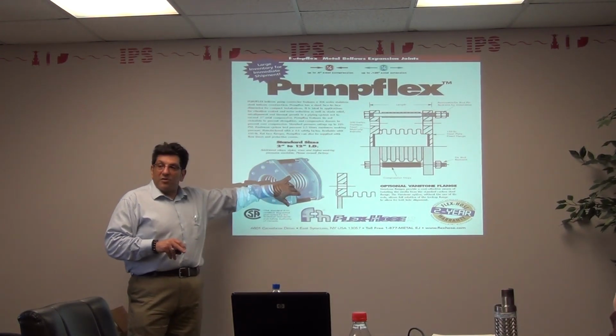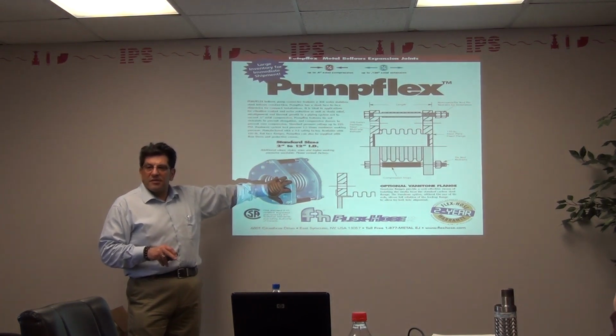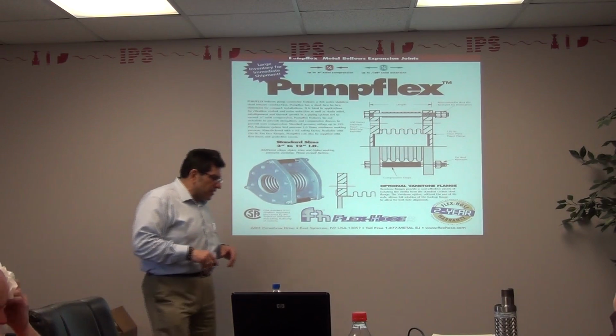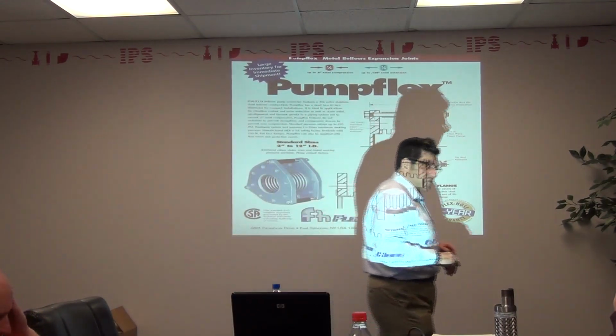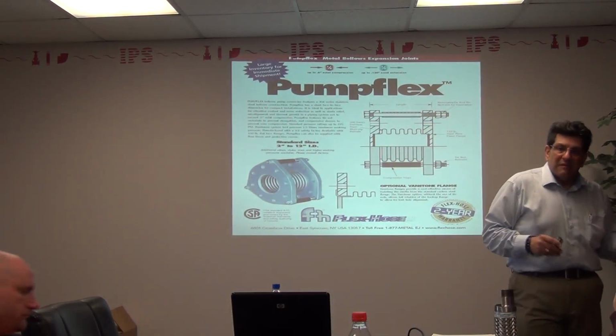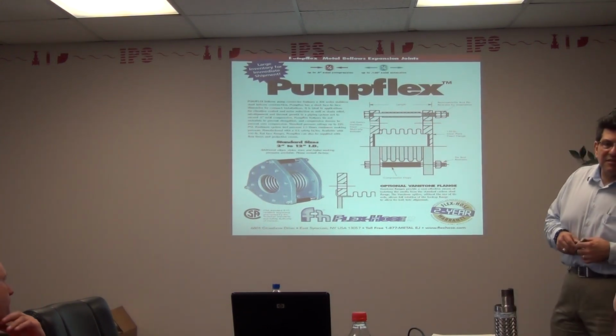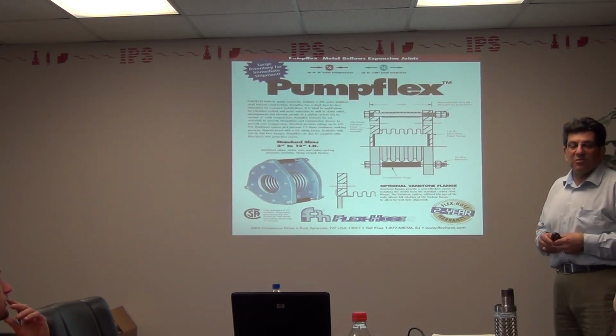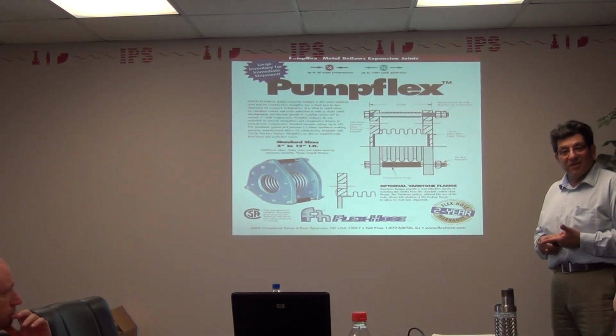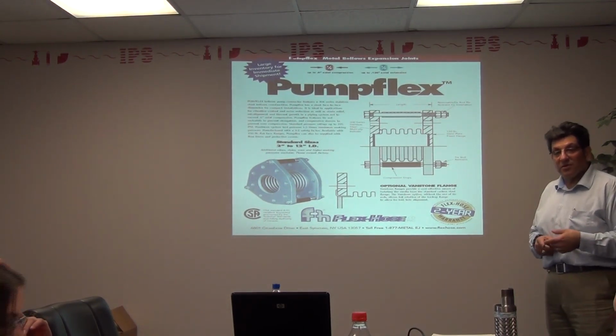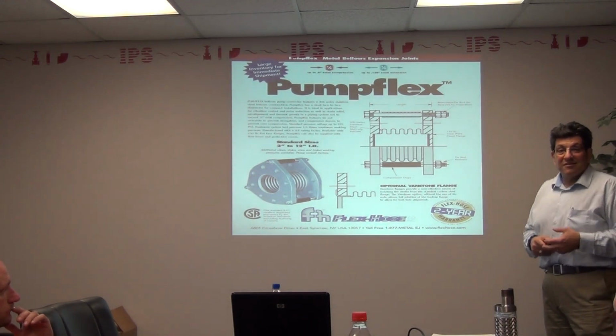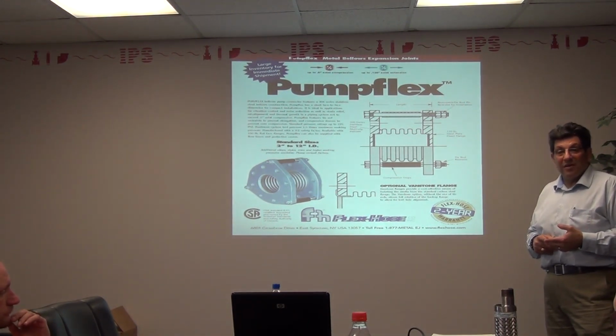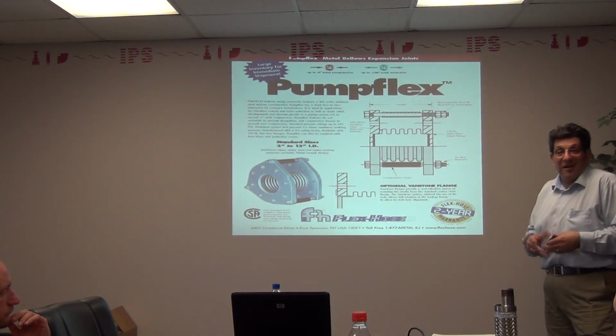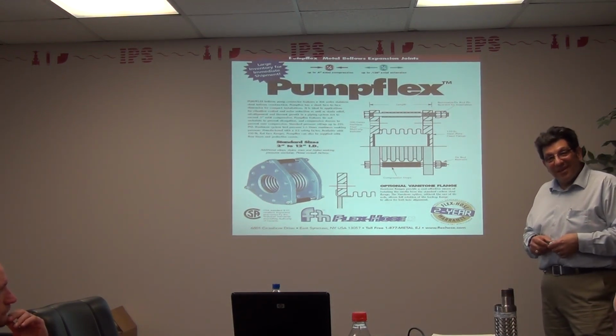It was for a university's second chilled water facility, where they were isolating all their equipment - chillers, pumps, big air handlers, all that stuff. The year before, they had used big hose, and when I looked at the drawing, I told them that was insane. They said it won't hit the pressures in the spec - well, we already have it in place. I said whoever told you that isn't giving you the whole story; that just isn't so, that would be new to our industry.